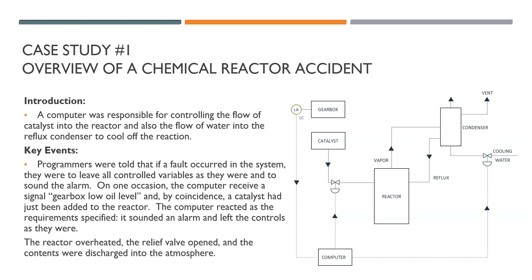So this is what they did. On one occasion, the gearbox sent a signal about a low oil level. That was not part of the process at all, and had no influence on it. However, because of the way the requirements were created, the computer sent the signal to the valve, and no more control on this valve was occurring. At the same time, the catalyst was flowing into the reactor, the reactor overheated, the release valve opened, and chemical content was discharged into the atmosphere.